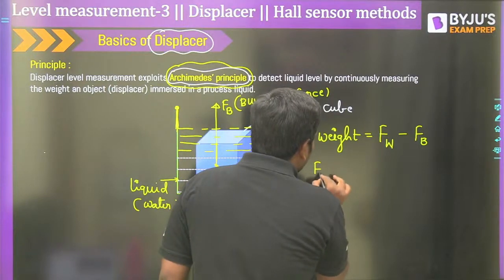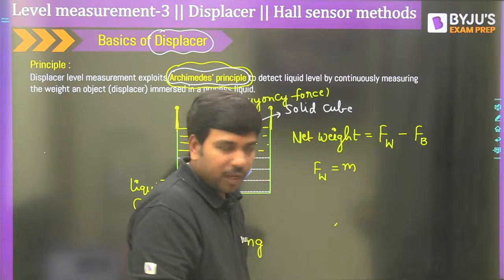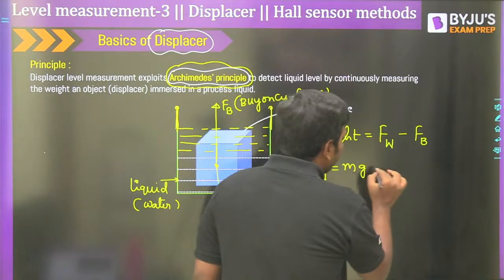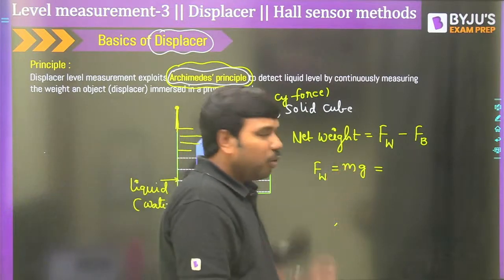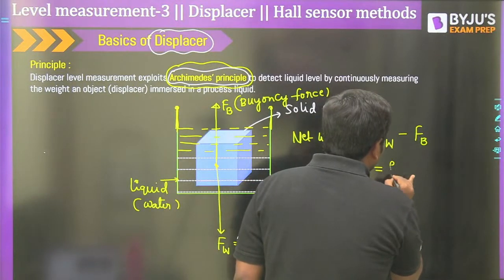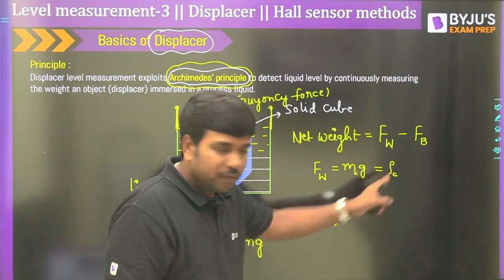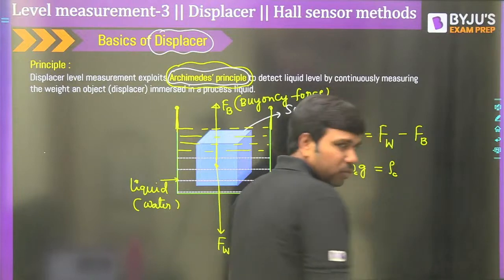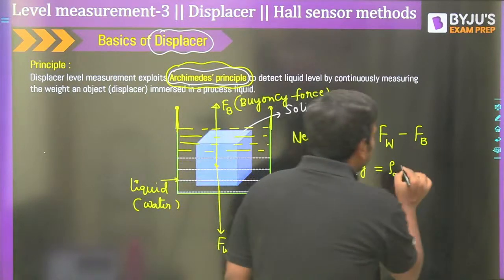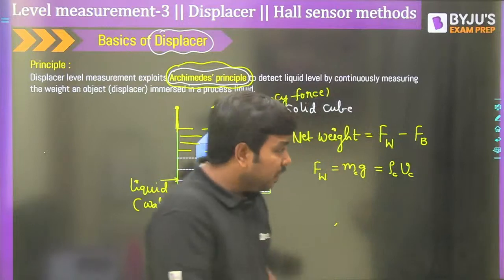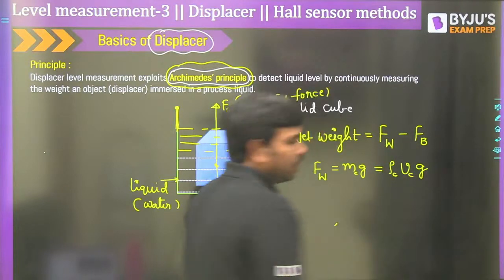So the relationship is: if the water level increases, the net weight decreases. More water level means the gauge rotates toward the minimum side. The calibration says: if the tank is empty, the needle is at maximum; if the tank is full, the reading is at zero. That is how we decide the level using this principle.